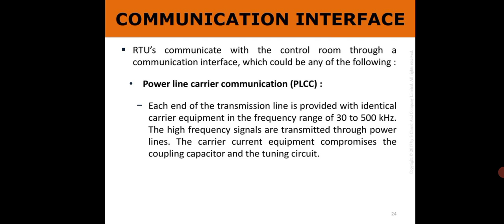Then, power line carrier communication (PLCC). Each end of the transmission line is provided with identical carrier equipment in the frequency range of 30 to 500 kHz. The high frequency signals are transmitted through the power lines. The carrier current equipment comprises the coupling capacitor and the tuning circuit.